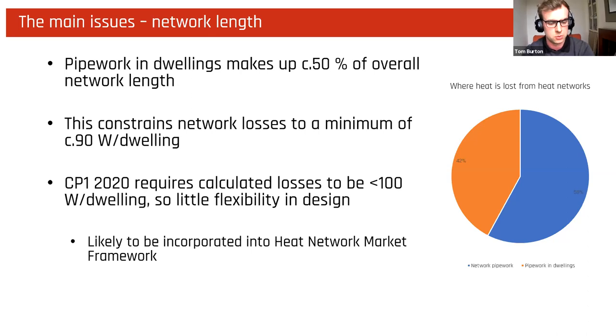And CP1 2020, which was also mentioned quite heavily throughout the first session, is going to require networks to have calculated heat losses of below 100 watts per dwelling. So this current configuration really doesn't leave you much flexibility in your design. You have to go quite heavy on the insulation and on performance to make sure you can stay within that performance metric. This is also going to be incorporated into the heat network market frameworks, or is likely to be, which again was spoken about during the first session. This may end up being a regulatory requirement to design to meet this 100 watts per dwelling. And again, within internal HIUs, that is possible, but difficult.